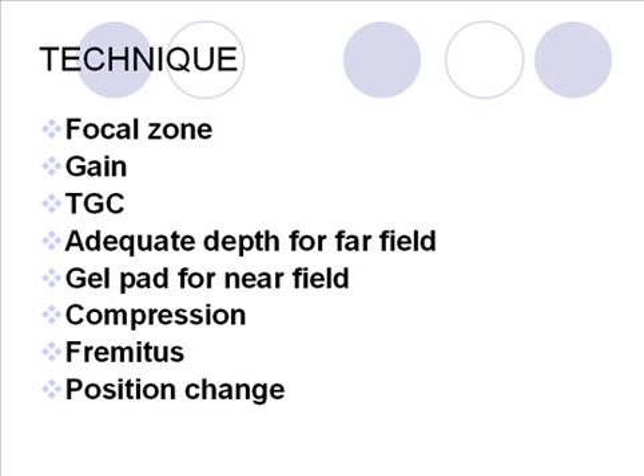Other than that, the fatty tissue should be kind of a charcoal gray color, or what my coworker likes to call it, a flannel gray. I like that flannel gray, because that's what it should look like. It shouldn't be black. It shouldn't be overly bright. It should be a dark gray so that you can judge everything against that.